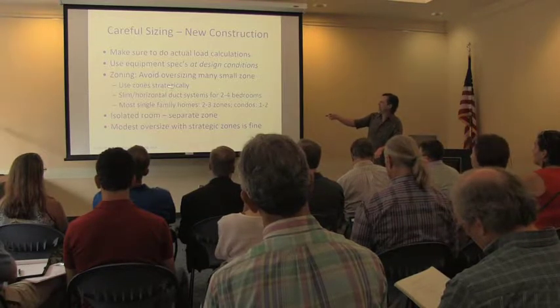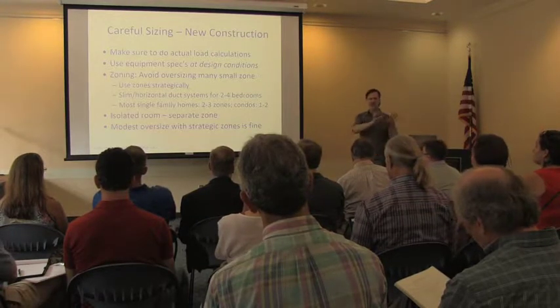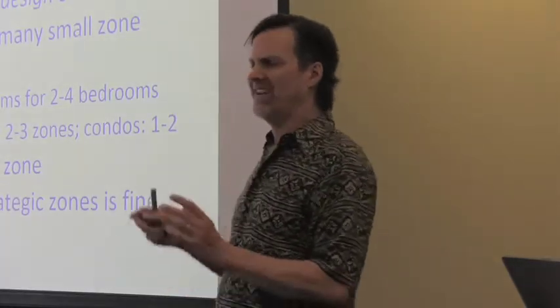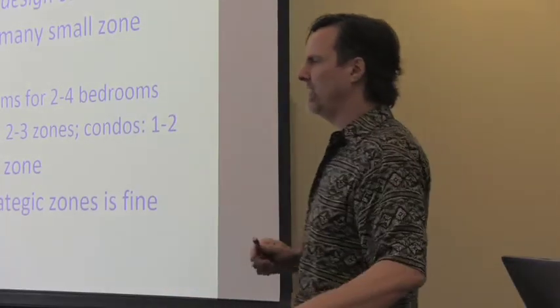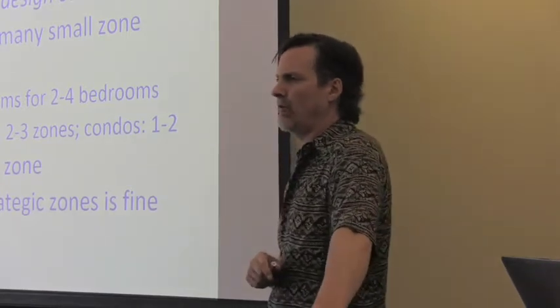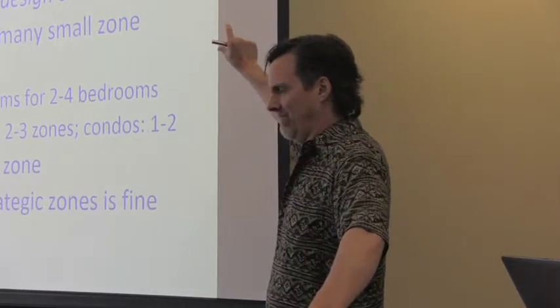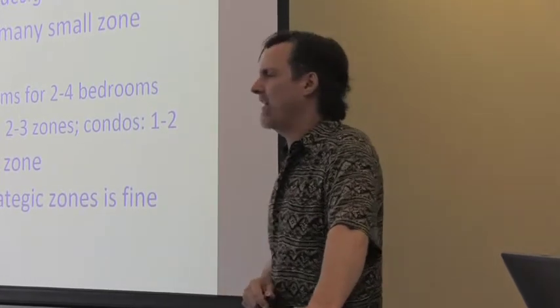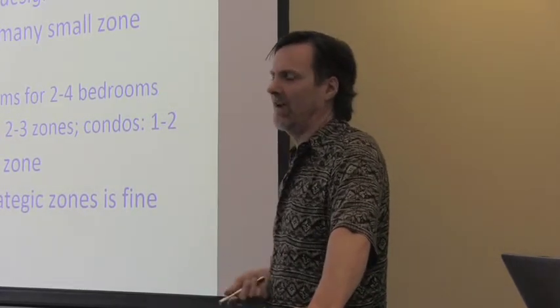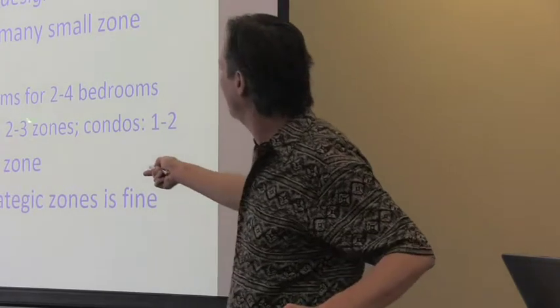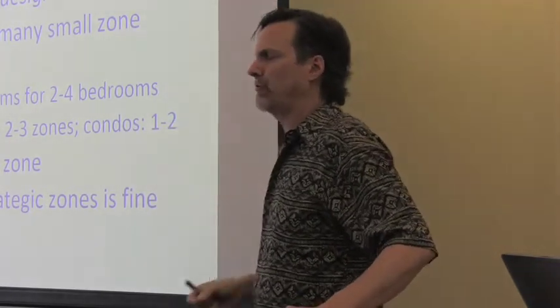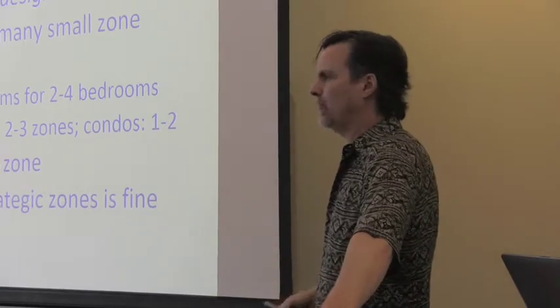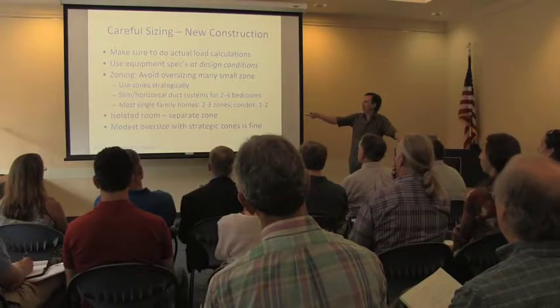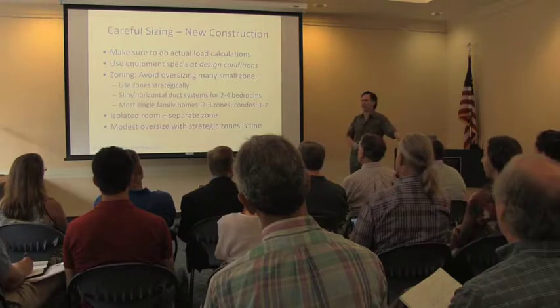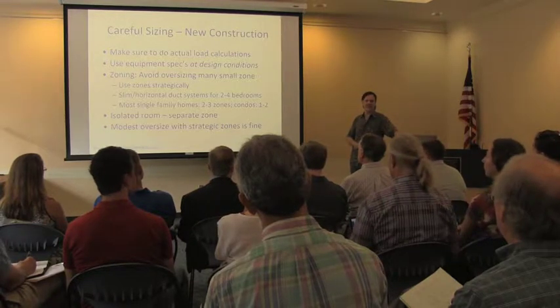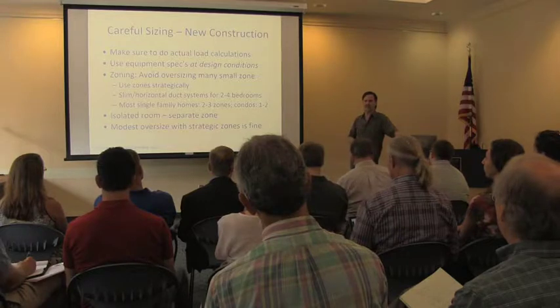One of the things that I often suggest is, instead of separate zones for small bedrooms, the energy loads in those bedrooms are probably 1,500 to 2,500 BTUs per hour, and the smallest heat pump indoor heads are 6 or 9,000 BTUs per hour, depending on the manufacturer and the product line. So you really would be oversizing for multiple bedrooms, and that can cause problems with the way the equipment operates. So we're really looking at small ducted systems if you're going to serve multiple bedrooms with small loads, as a more cost-effective way to do that and actually operating more efficiently.